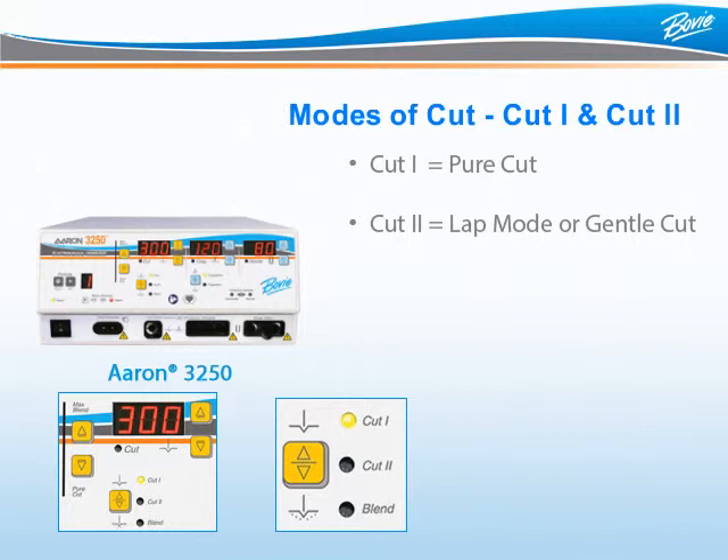Cut 2 is used in laparoscopic and microsurgery procedures to reduce the likelihood of alternate site burns. When in Cut 2 mode, the Aaron 3250 offers up to 300 watts of cutting power.